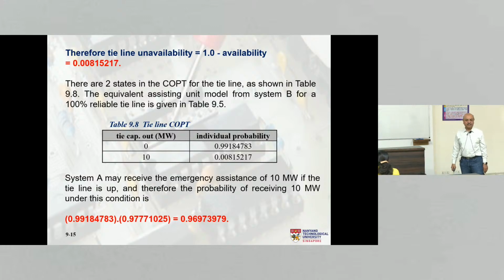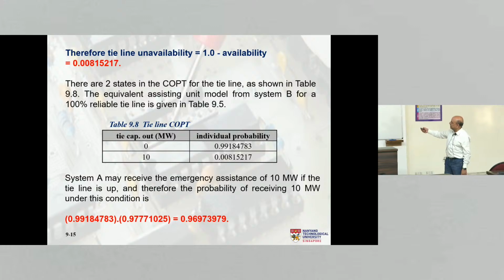Unavailability and availability of the tie line is known. So if I want to transmit 10 megawatt, the probability when the tie line is fully reliable is known to me, and the probability when the tie line is not available is known to me. So I can multiply those 2 probabilities and I get this individual probability. Similarly, tie line capacity out 10, the probability is 0.0081. So this is my new transmission line constraint model. I can still get only 10 megawatt assistance when the transmission line is up, and therefore the probability of receiving 10 megawatt is 0.9918 times 0.9777, right?